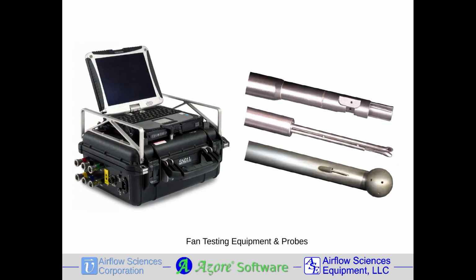A variety of testing standards exist for fan performance testing, including ASME PTC 11, AMCA 203, and AMCA 803. Whether you have an axial, mixed flow, or centrifugal fan, these standards detail how to perform the test and the type of instrumentation required. By utilizing a standardized methodology, the end user can ensure consistent and reliable results across different manufacturers and test sites. The test specifications allow for standardization, accuracy, and reliability in the assessment of fan performance.